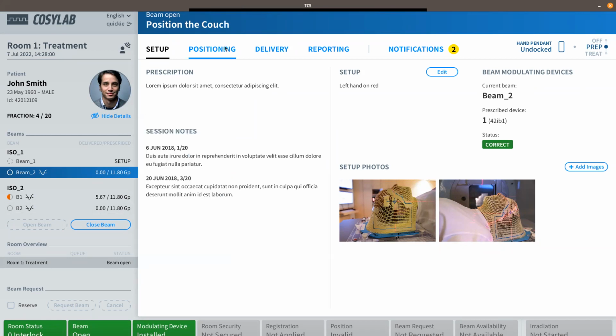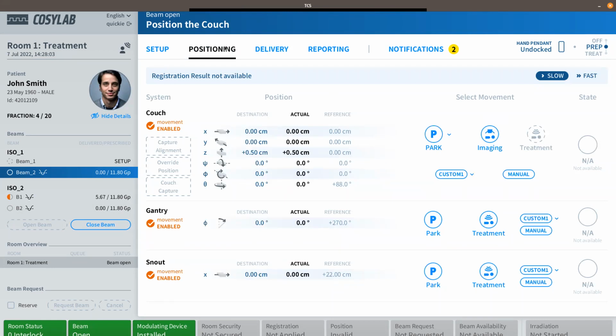And the next step now will be to go to positioning tab, and we will move the couch into the imaging position. We will do this by using two steps. We will use TCS to schedule the movement, and then we will use the hand pendant, that is basically a remote controller for the system, to actually execute it. So I will press two buttons. First one on the TCS to schedule the movement, and then actually two on the hand pendant to perform the movement.